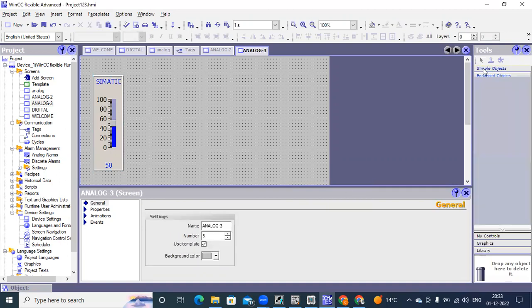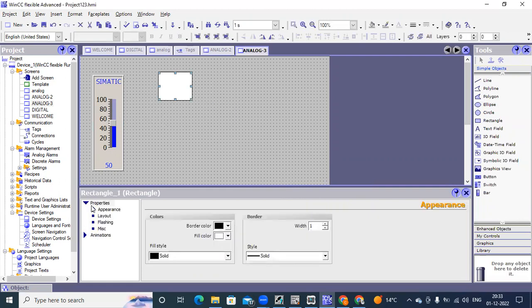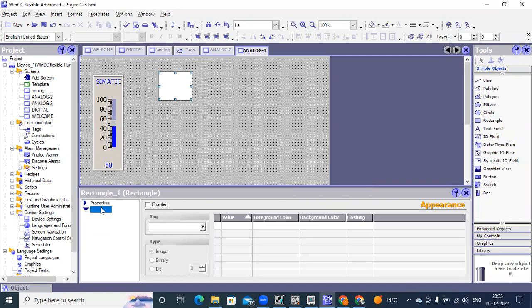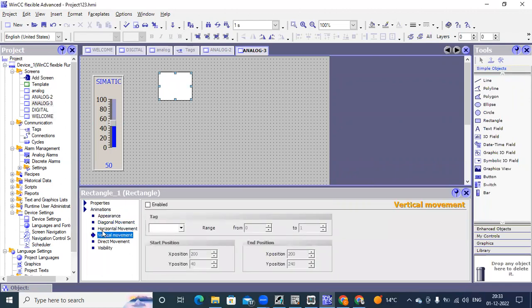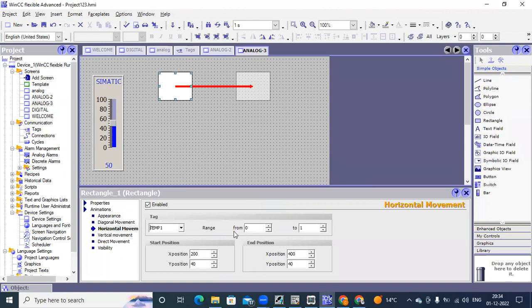Now I take a block here — a rectangle or something. Under animation for this block, you are having diagonal movement, horizontal movement, vertical movement options. If you want to move this object as some vertical or horizontal movement, you can enable that property. Select the tag and some range — from 0 to 100. Some range you can set, starting position x and y — that is your window position — from where you want to move and how much you want to move, that you can set here. You can see it is showing that range — from here to here it will move.